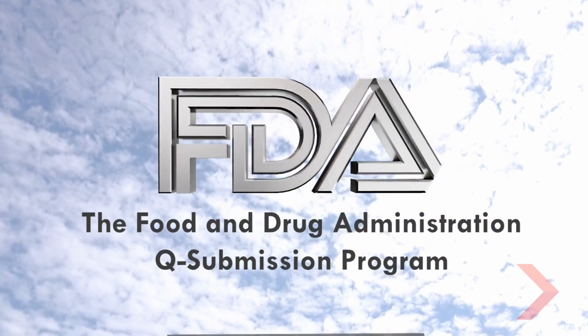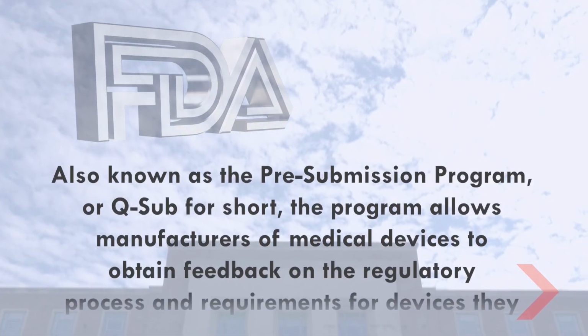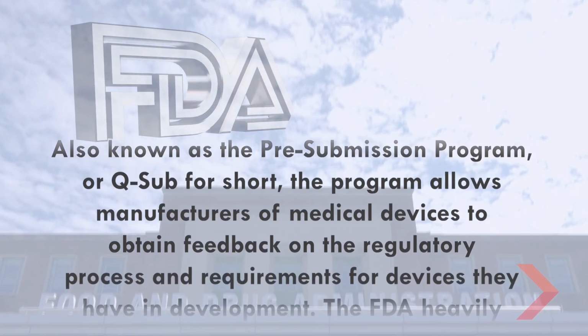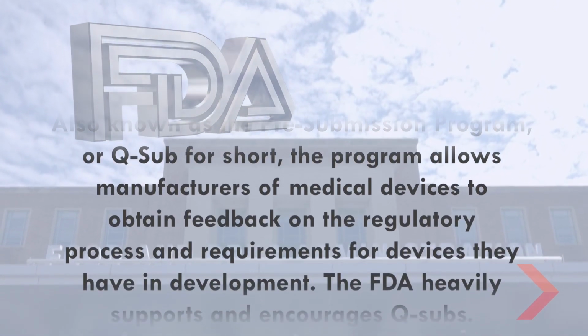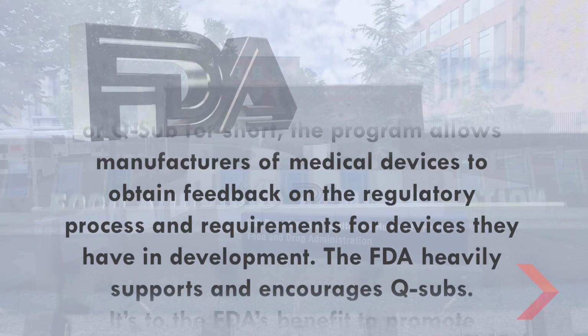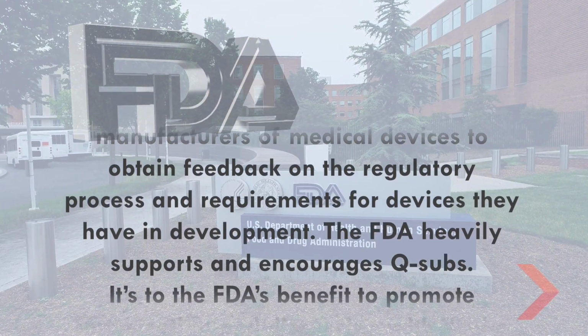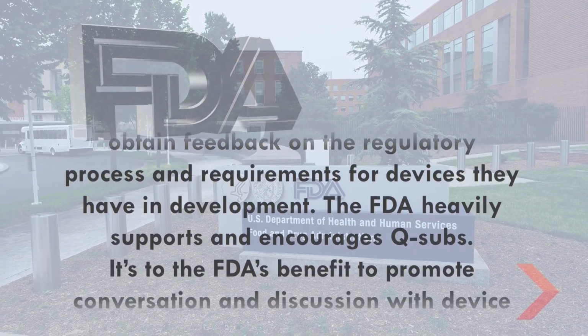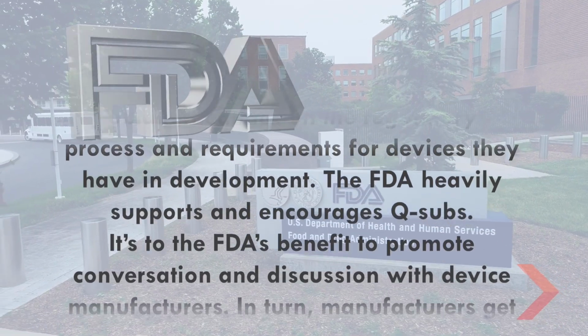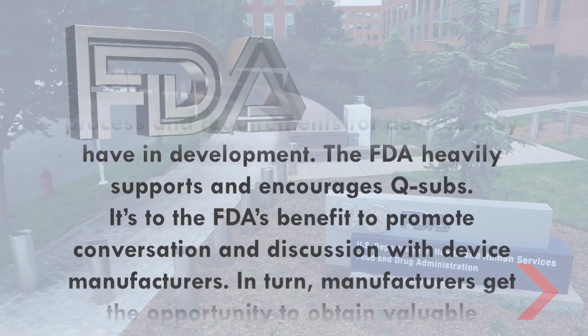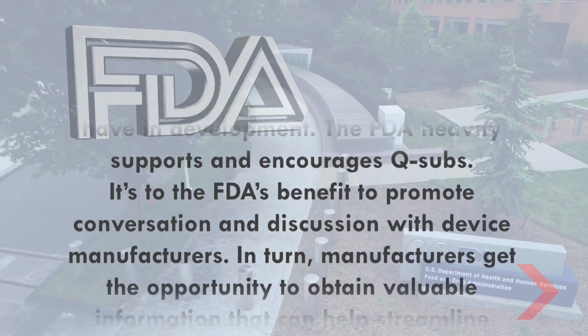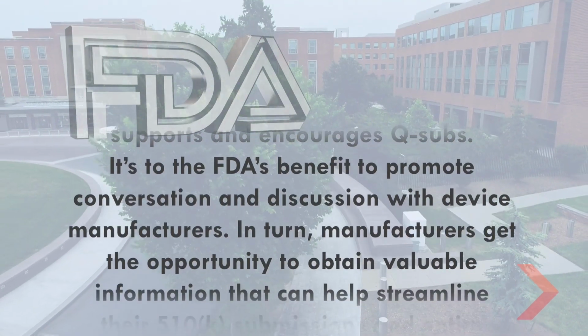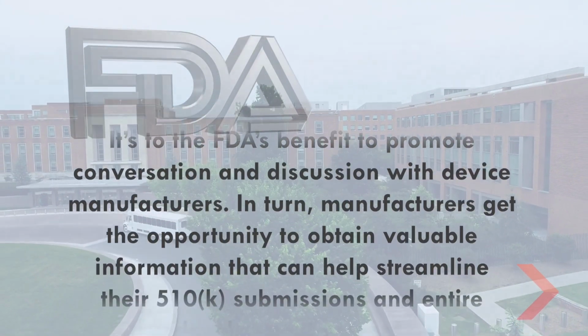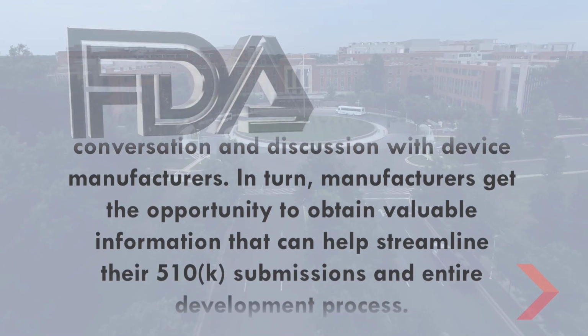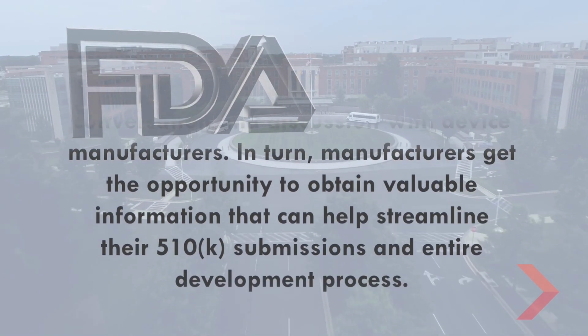The Food and Drug Administration Q-Submission Program, also known as the Pre-Submission Program, or Q-Sub for short. The program allows manufacturers of medical devices to obtain feedback on the regulatory process and requirements for devices they have in development. The FDA heavily supports and encourages Q-Subs. It's to the FDA's benefit to promote conversation and discussion with device manufacturers. In turn, manufacturers get the opportunity to obtain valuable information that can help streamline their 510(k) submissions and entire development process.